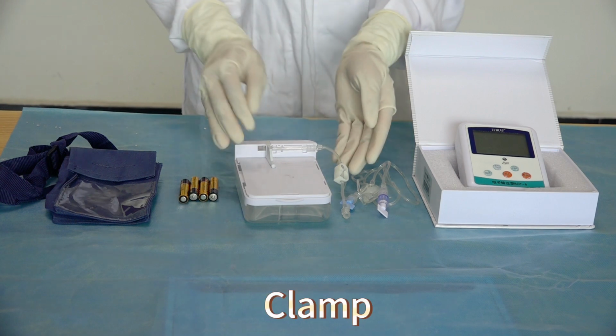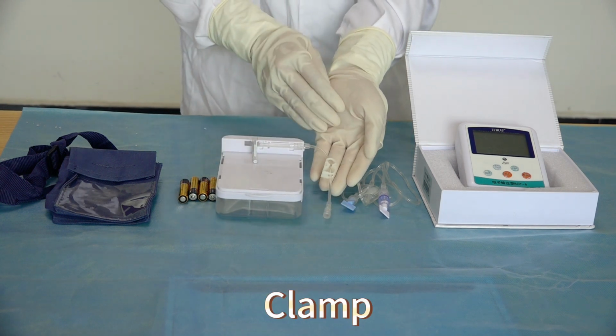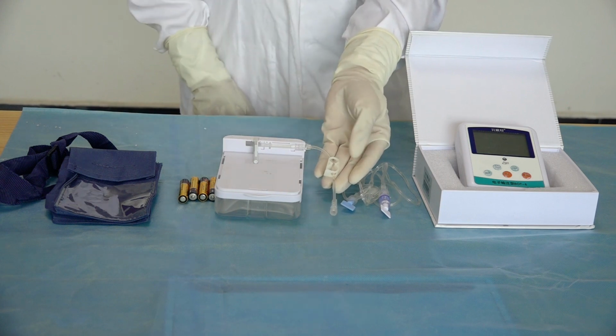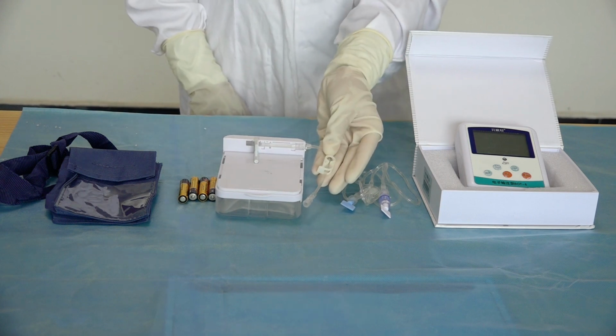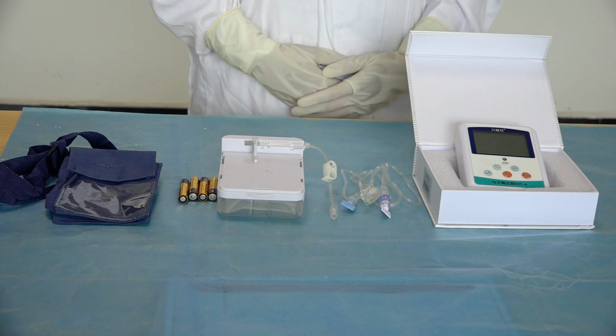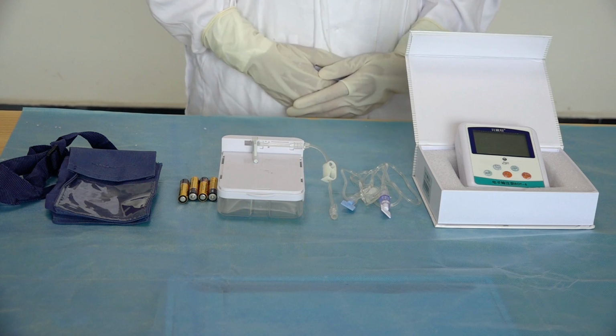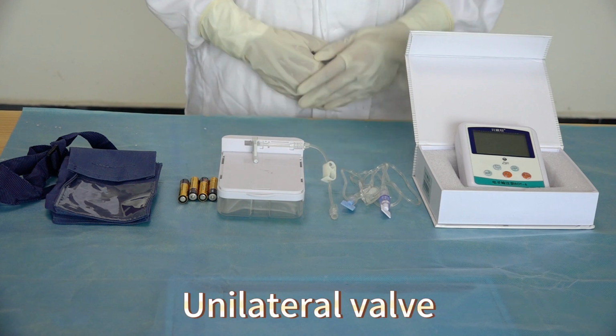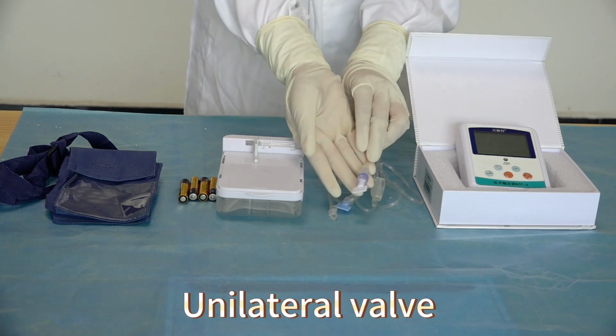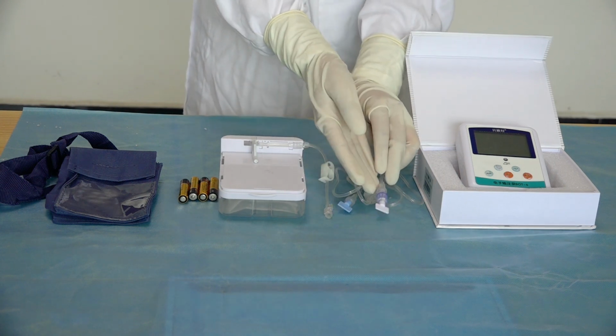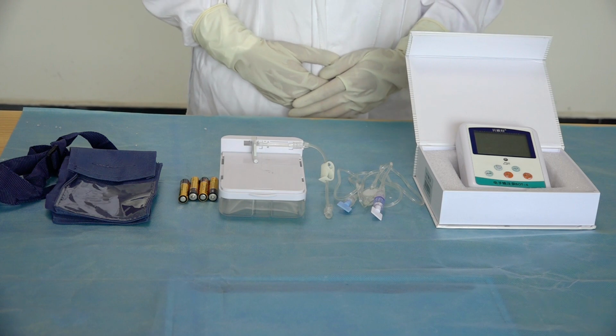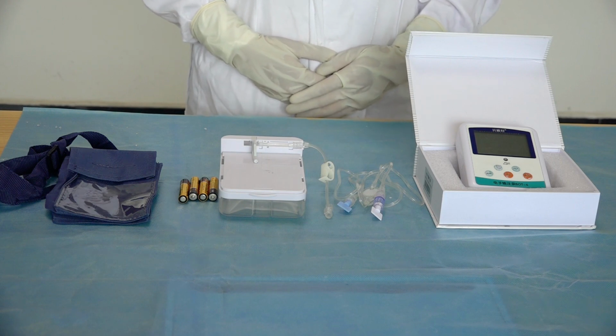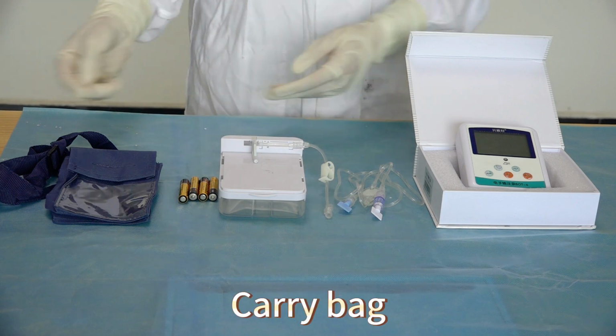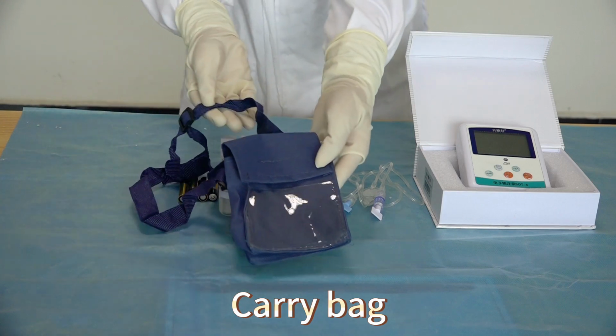1. Clamp. When the electronic infusion pump makes alarm, close the clamp, which can effectively stop the infusion. 2. Unilateral valve. Prevent backflow of blood. It can effectively prevent the blood from backflowing into the pipeline. 3. With special carrying bag for the pump.